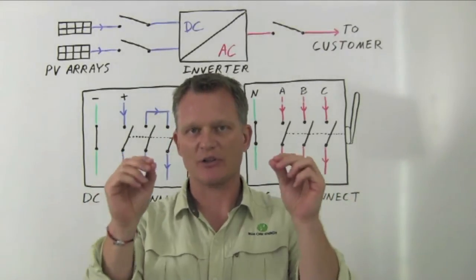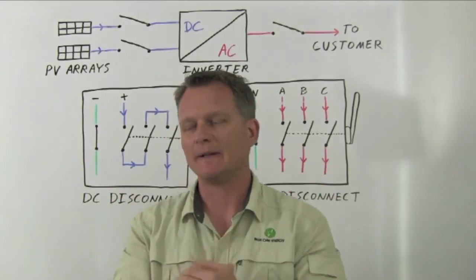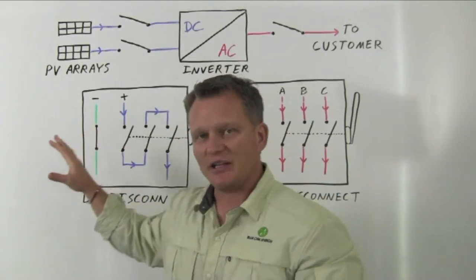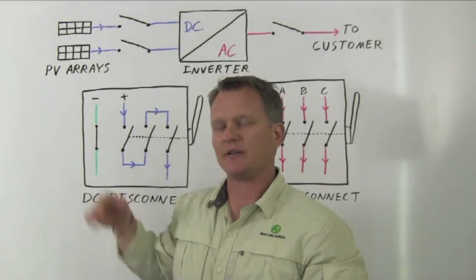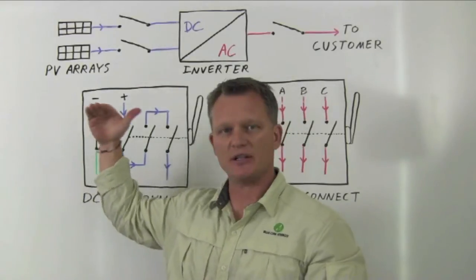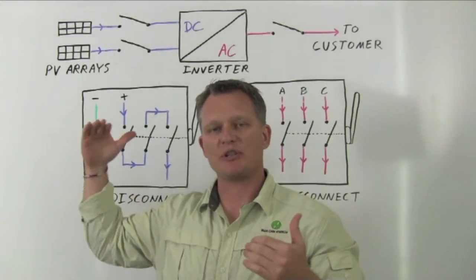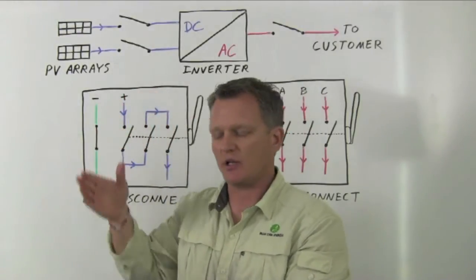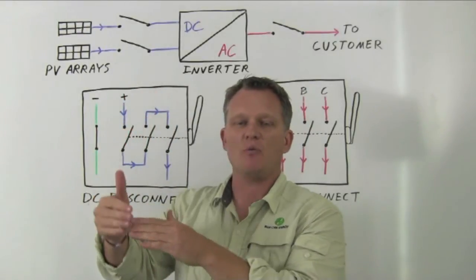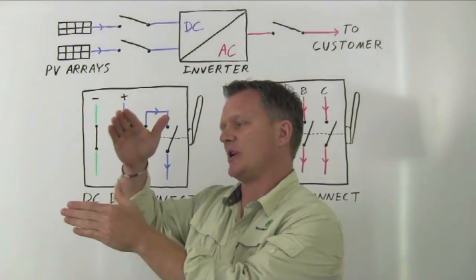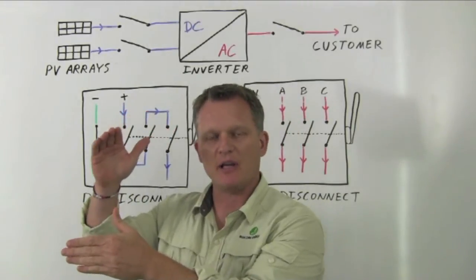That's not the case with DC current. A DC current is a constant value and stays persistent. When you open up a DC disconnect switch, an arc forms and it wants to continue, and you have to open it with even a larger air gap to get it to extinguish.